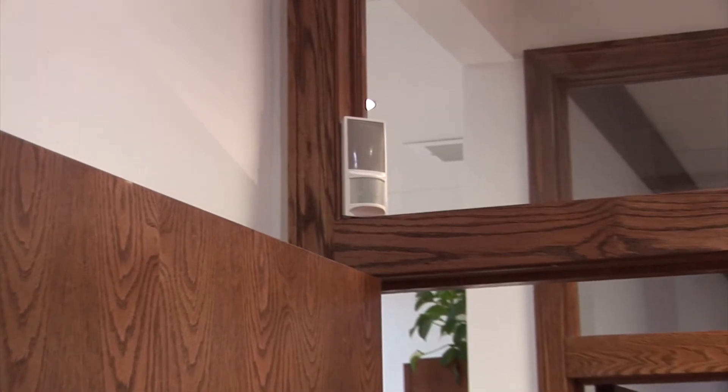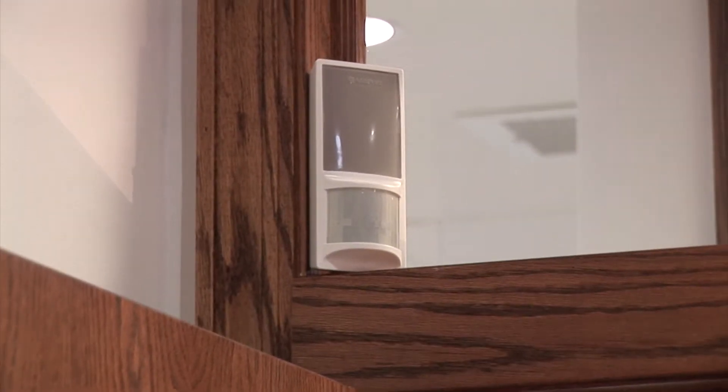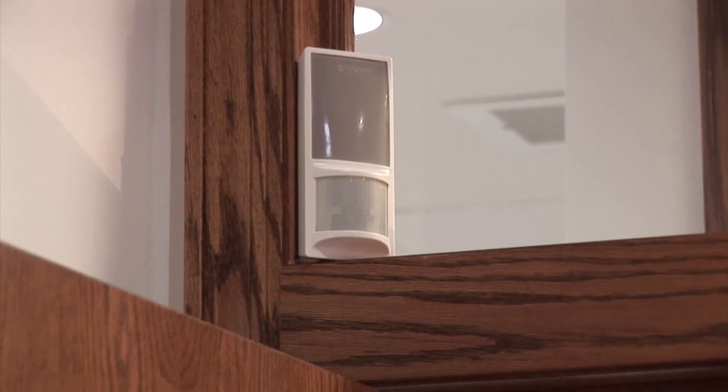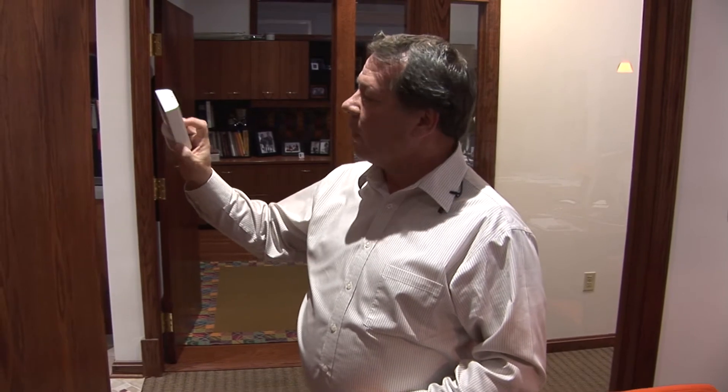The lights in the room are controlled with an occupancy sensor, and this is wireless — it's an EnOcean-powered occupancy sensor. It gets its power from the sunlight and the LED lights coming into the room. It charges and is good for three days in complete darkness. When someone walks into the room, it turns the lights on and off — works as a standard occupancy sensor, but no wiring required.